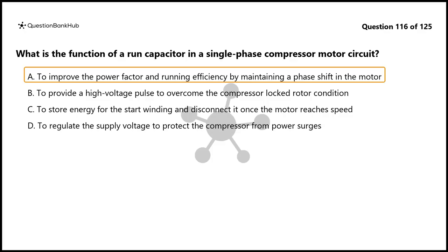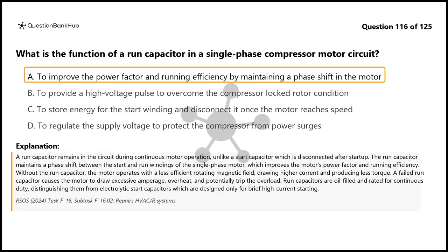The correct answer is A. A run capacitor remains in the circuit during continuous motor operation, unlike a start capacitor which is disconnected after startup. The run capacitor maintains a phase shift between the start and run windings of the single-phase motor, which improves the motor's power factor and running efficiency. Without the run capacitor, the motor operates with a less efficient rotating magnetic field, drawing higher current and producing less torque. A failed run capacitor causes the motor to draw excessive amperage, overheat, and potentially trip the overload. Run capacitors are oil-filled and rated for continuous duty, distinguishing them from electrolytic start capacitors which are designed only for brief high-current starting.